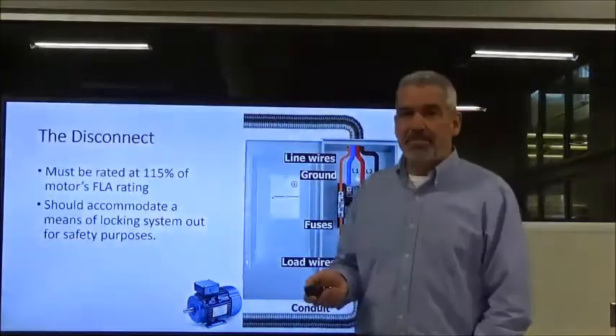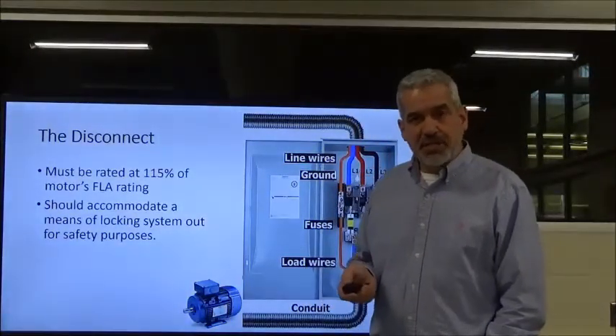So that was slow motion just to give you an idea of what the arcing looks like. Technically, that equipment there is not designed for that arcing either. They were opening and closing it under a load. So a couple more things about the disconnect before we move on.